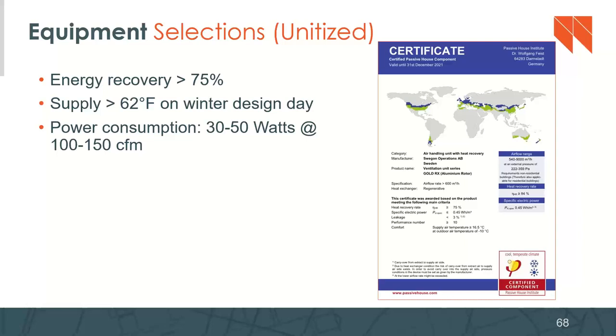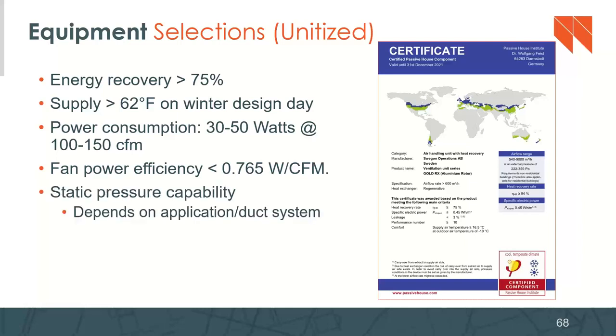Other considerations: the power consumption. So not only the efficiency of the recovery, but also how much electrical energy it's going to use to move that air around. Usually we're looking for something like 30 to 50 watts when moving 100 to 150 CFM of air. That is a fan power efficiency of 0.765 watts per CFM.